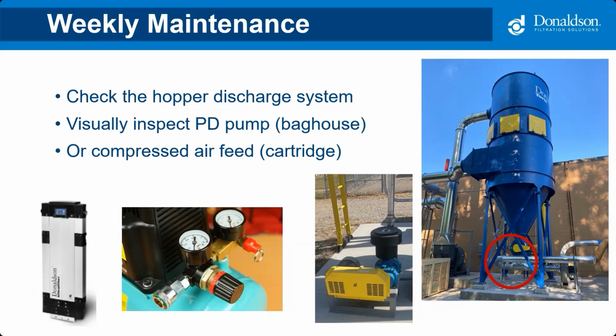For a cartridge collector, cartridge collectors don't use PD pumps typically. They use compressed air from your operations compressed air system, right, that your factory is using. It's good just to make sure the compressed air feed is still set properly. Typically on a cartridge collector, that's somewhere between 90 and 100 PSI, but check your manual for the specific settings required. I've seen where sometimes to save energy, maintenance folks or energy folks in the factory that are doing audits will turn the compressed air feed down.